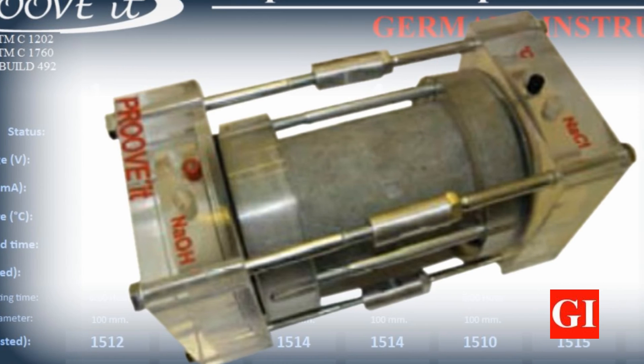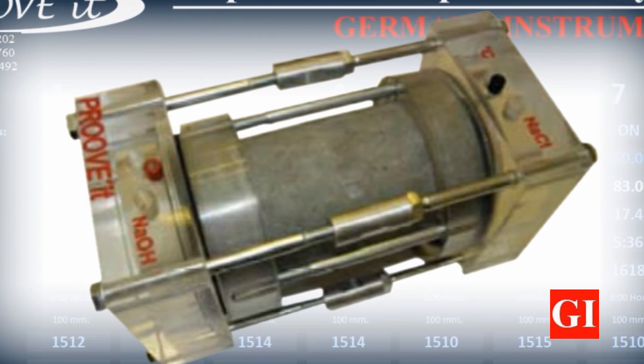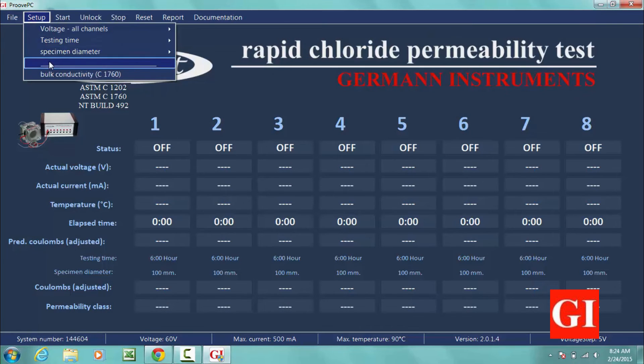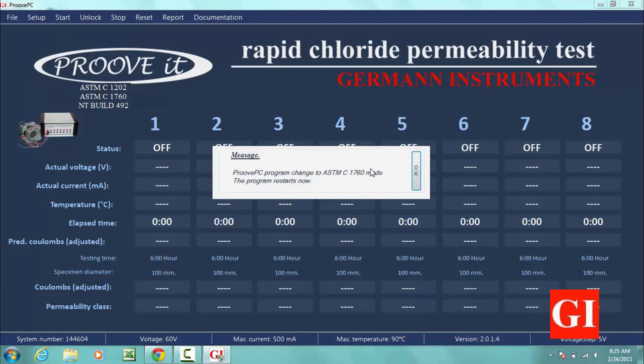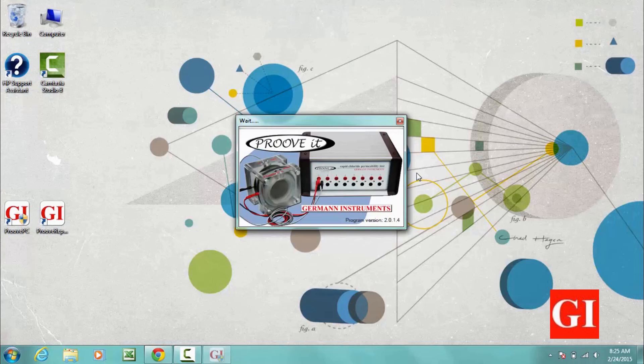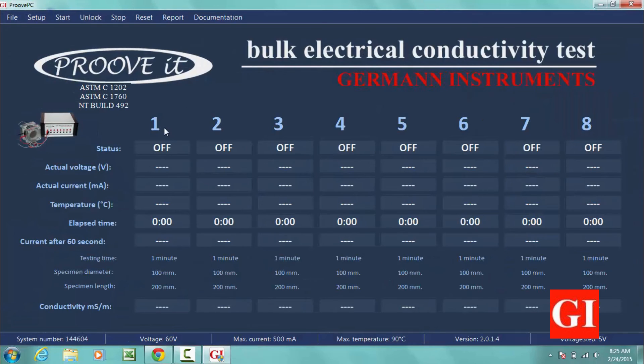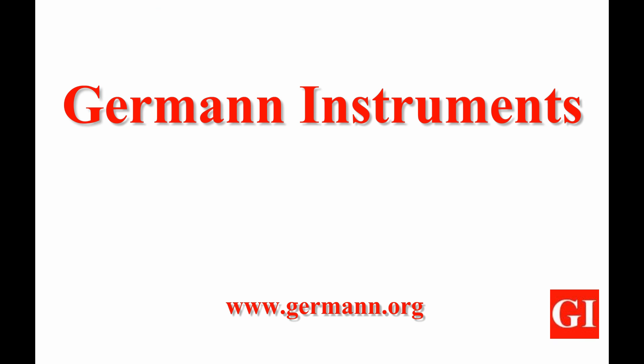ASTM 1760 Bulk Conductivity or Resistivity requires a cell with longer bolts to fit 100 by 200 mm cylinders. When using this mode, the testing time will be restricted to 1 minute, and voltage, diameter, and length of the specimen have to be defined by the user. As always, Germann Instruments provides the best options for concrete professionals.